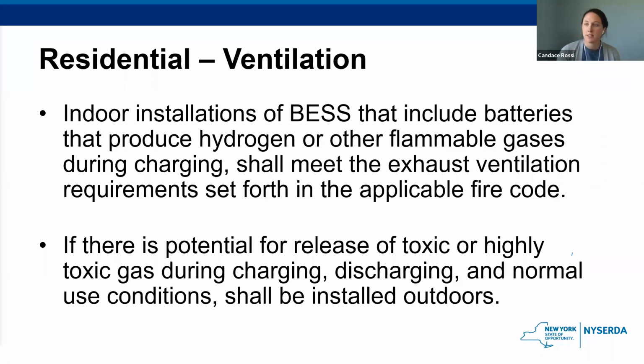So here we have the residential ventilation requirement. Indoor installations of storage that includes batteries that produce hydrogen or other flammable gases during charging shall meet the exhaust ventilation requirements set forth in the applicable fire code. So like I had said previously, lithium-ion batteries do not basically produce hydrogen or flammable gas during normal operation.